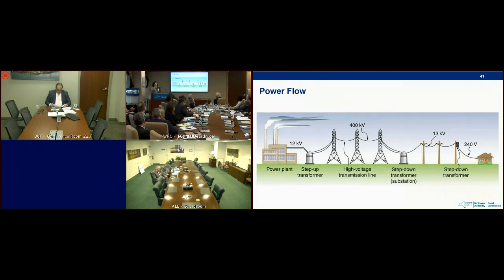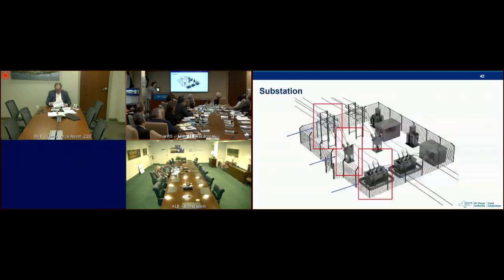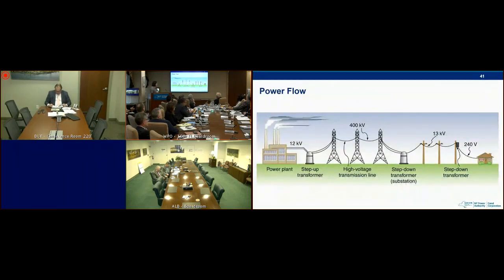Continuing to dive a little deeper in terms of power flow - a quick, simplified picture of how power gets from us to customers. Power typically for us comes out of our generating stations at 13.8 kV, and then the voltage gets stepped up by the generator step-up transformers and continues on to our transmission lines, shown here as 400 kV in this pictorial, reflecting the voltage ranges I mentioned earlier. The voltage needs to be stepped up so it can be carried long distances. The transmission lines then enter a substation where the voltage is stepped down, so it can ultimately be connected to distribution lines and carried to a customer at a much lower voltage.